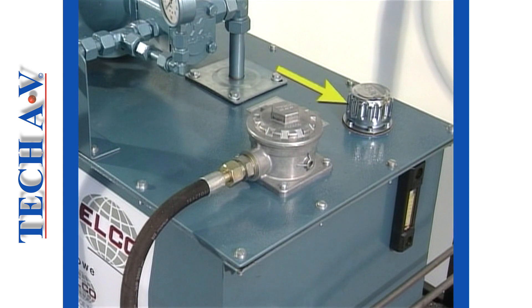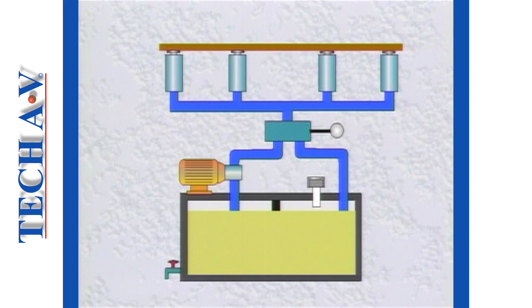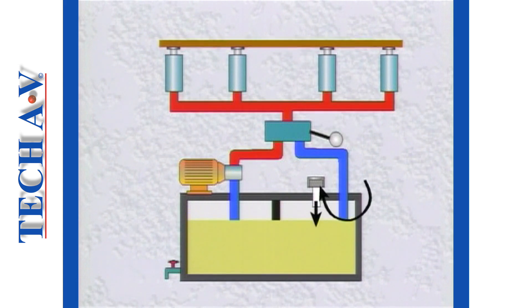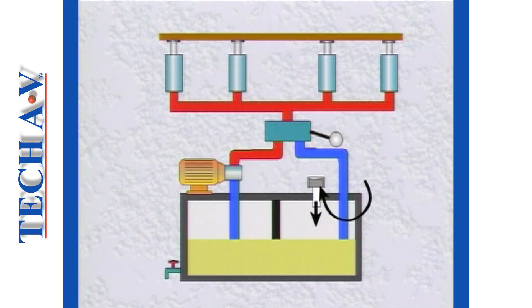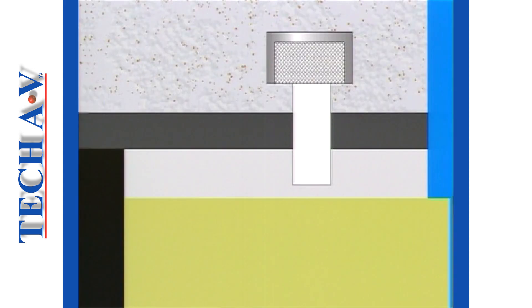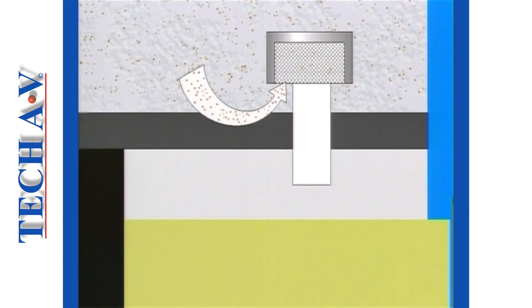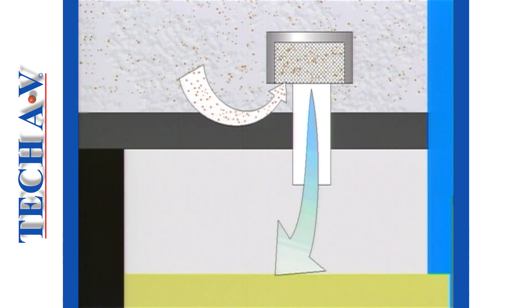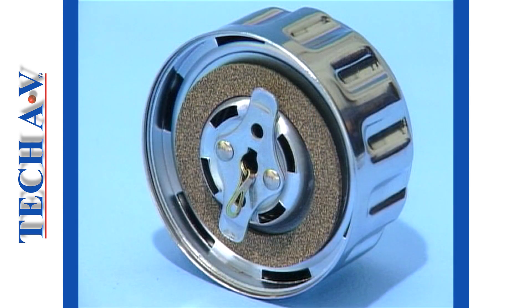The suction side of a system starts at the receiver or tank, beginning with the breather. Air enters a tank via the breather whenever the oil level drops during operation and escapes again each time the level rises. The air intake filter, commonly situated in the filler cap, traps any airborne dirt particles, preventing them from entering into the oil. The air filter, or breather, is a very important part of the total filtration system and must not be neglected.